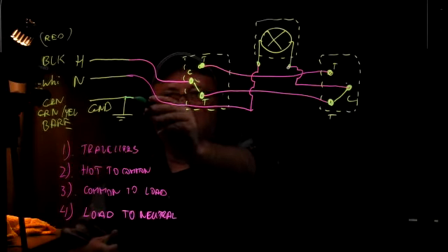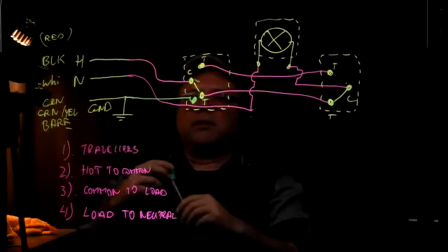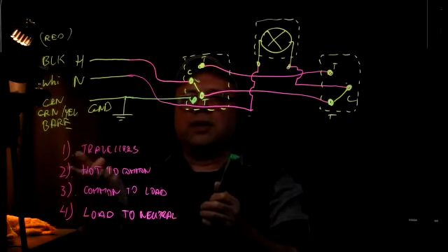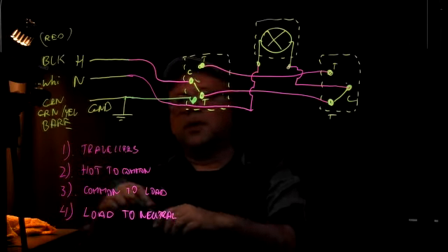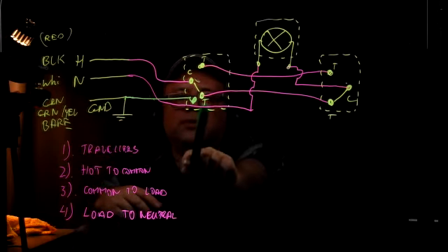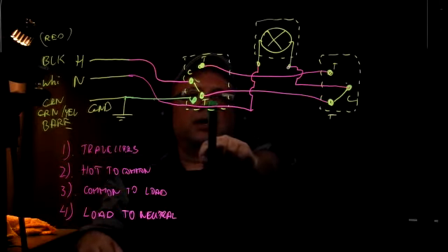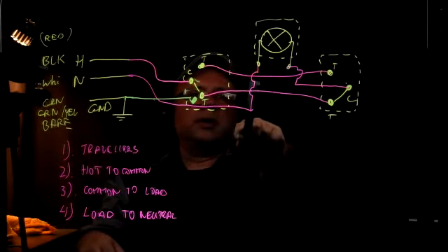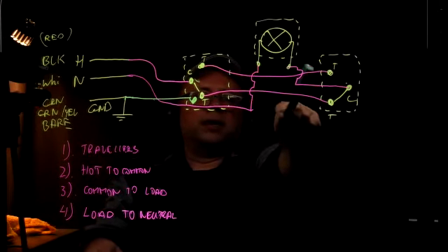If it's EMT, it's going to have to terminate somewhere here. So, do we have a neutral white wire passing through every box? Let's analyze that. Here we have a neutral. It goes to this first device box. Now we're continuing. This device box, yes, neutral goes there, but there's no direct neutral here.